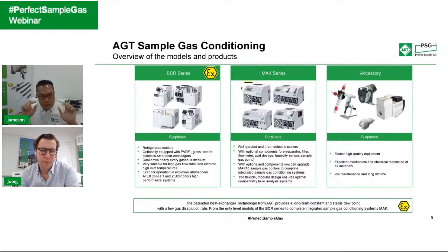So in between this sentence, there are small little details, but in this webinar we just want to say that when we design a sample gas cooler, we design it in such a way that the retention time in the cooling has to be fastest, so that the amount of soluble gases that wash out is minimized. So it gives the sample to be the most representative. That is how one gas cooler differs from another.